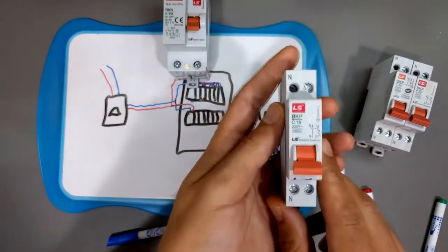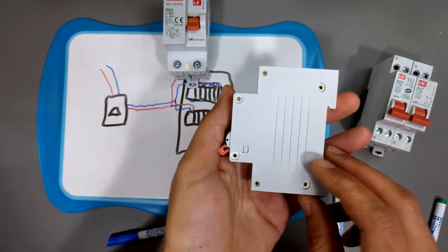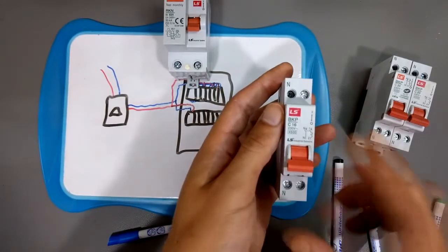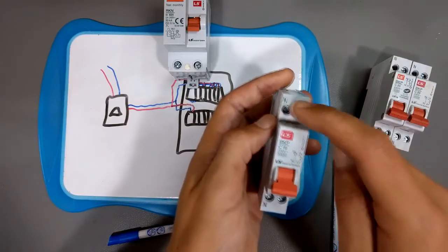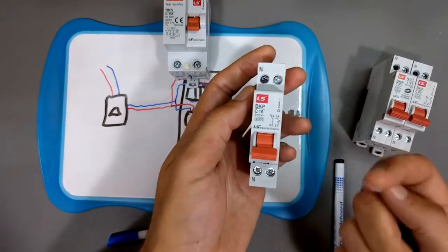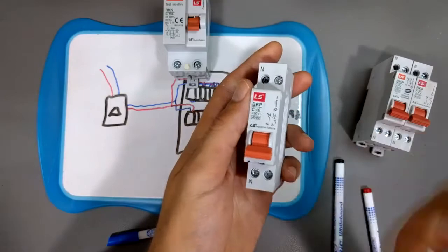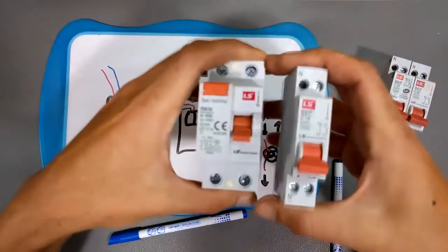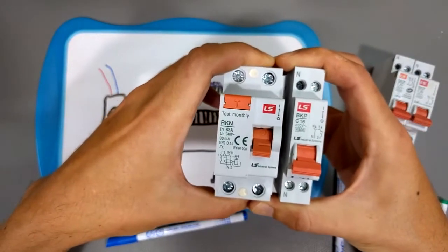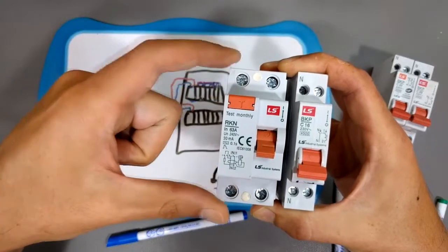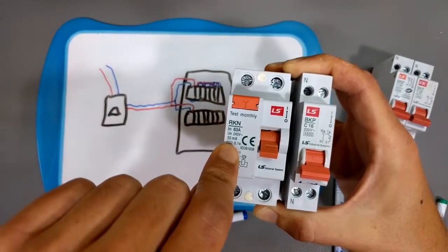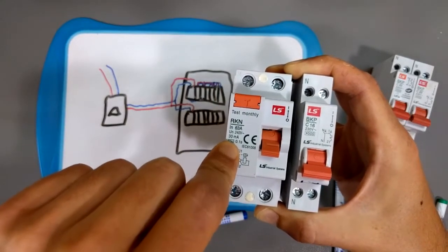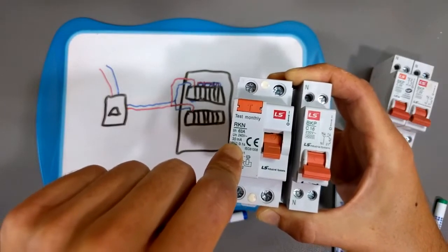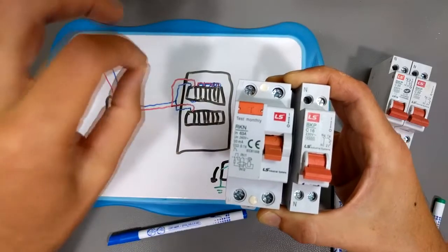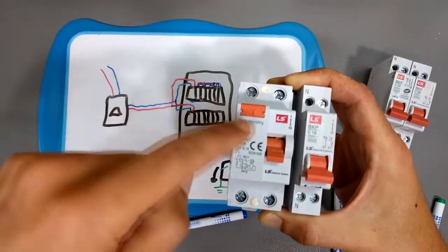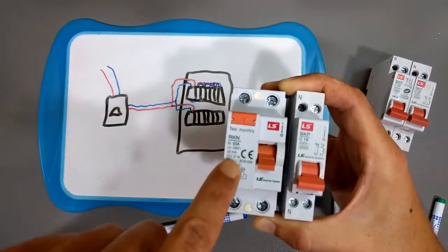So these are typical generic circuit breakers, which are usually thermal magnetic breakers, and they are for overcurrent conditions. They don't protect against electrocution. They also protect against a short: if you have your live and your neutral at the output and you short the wires together, obviously you'll have a very large current flow, and usually the magnetic portion would kick in because it'd be a really big current and it'll flip off. So essentially you have these two types of breakers, which each are basically a fancy light switch. And this guy protects mostly against electrocution. He detects the 30 mils of leakage current to protect against electrocution, as well as certain device faults. Sometimes you have a washing machine or something, and there's leakage current, and it's a minor fault, but this guy detects it and he'll trip because there should not normally be lots of leakage current.